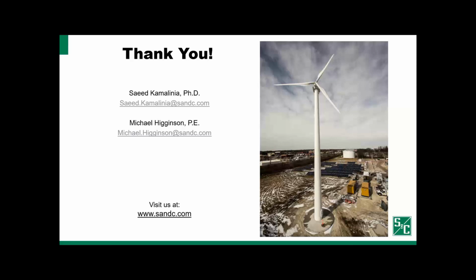Negative sequence current is essential for system operation, and as inverter-based resources become a more significant component of the total generation, it's more and more important that they carry their share of the unbalance in the system and are capable of supporting the system through unbalanced faults, et cetera. So I think it's very valuable, and it's something that can be important to enabling more inverter-based resources to penetrate the system if they can support negative sequence current output.